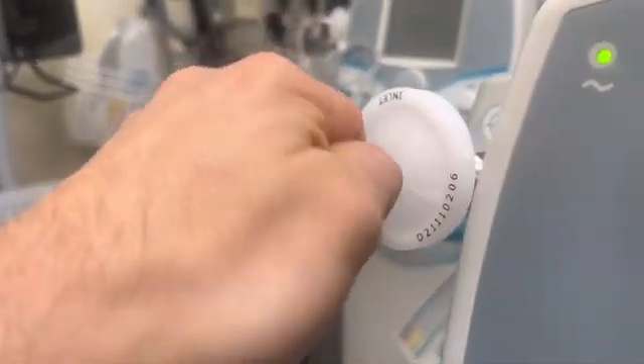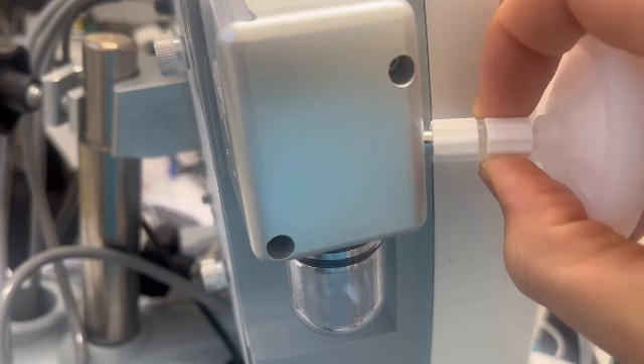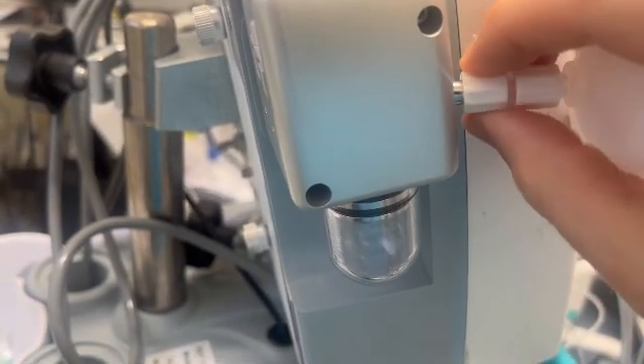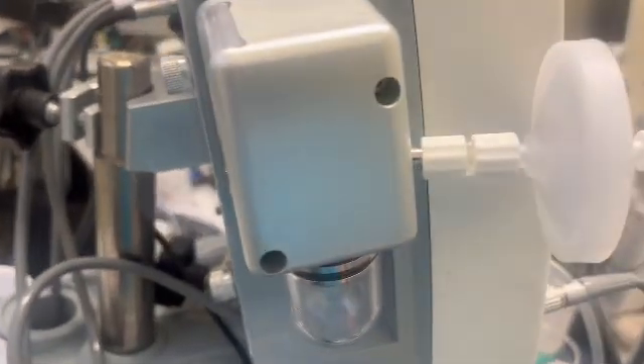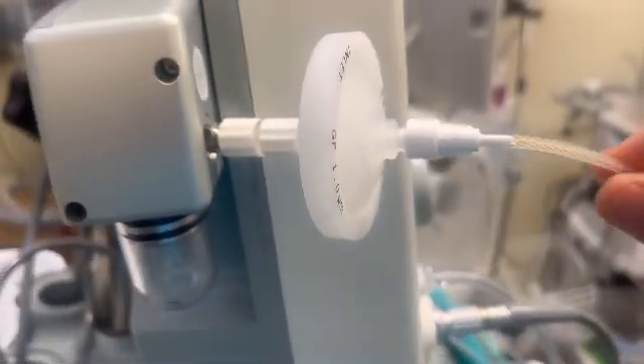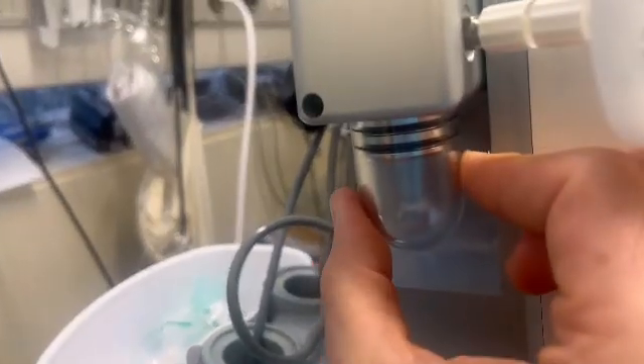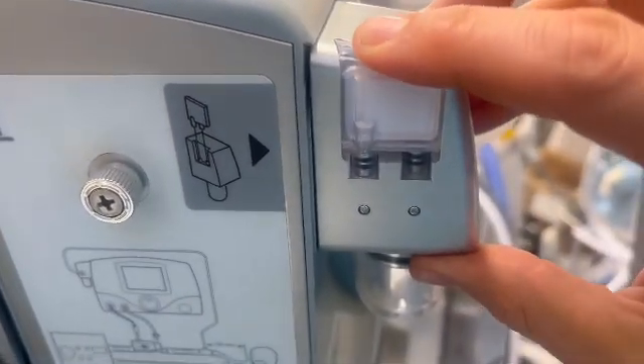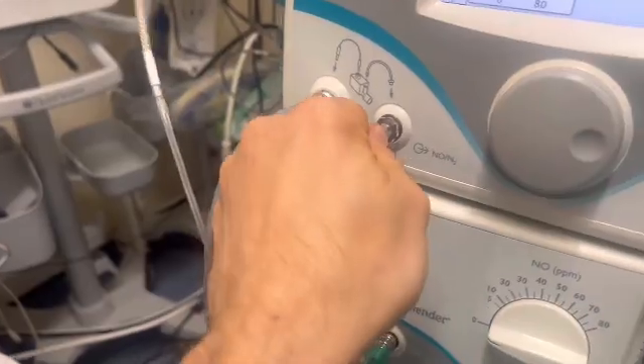Before you start doing any pre-use checks, you should make sure that all your disposables are connected securely. Particular attention should be given to the filter and the connections between the sample line outlet and the filter. The water trap is not disposable, but you should make sure it's on tightly. And the water separation cartridge should be securely fitted. Ensure the clear nitric injection tubing is securely connected to the machine and the injector module.